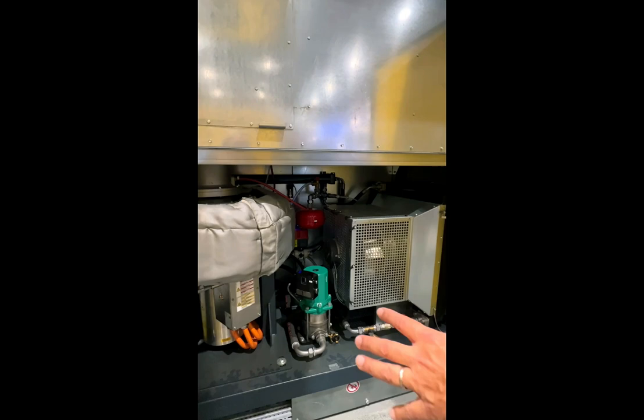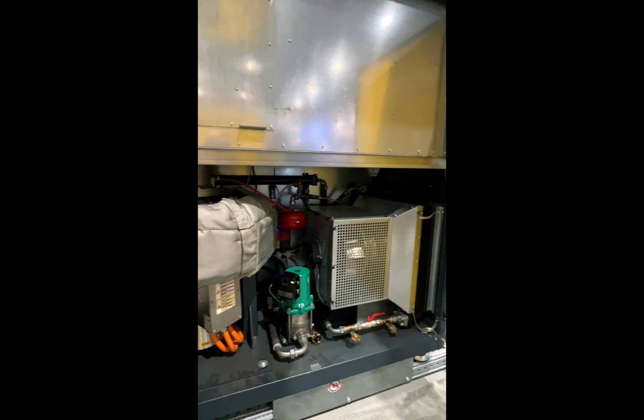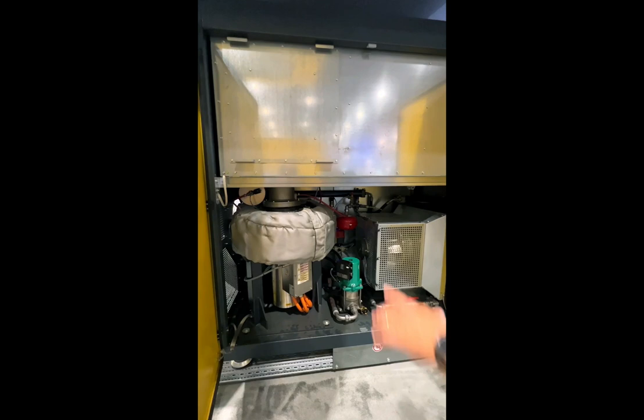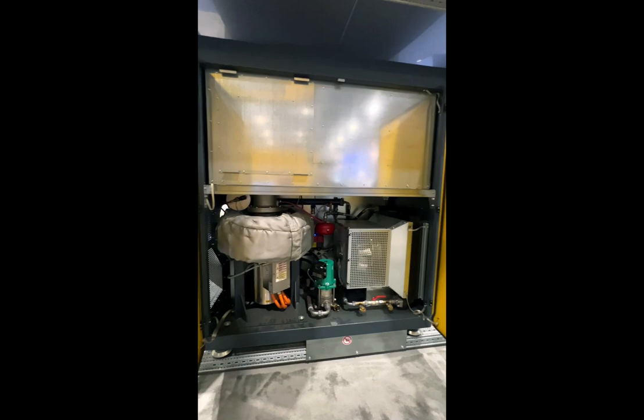Here is your motor and impeller combination. This is a magnetic-style bearing, so you have a shaft inside that motor levitating on a combination of permanent magnets and electromagnets. The electromagnets are controlled by the bearing controller on the opposite side. You're taking flow and temperature measurements here with transducers wired through the panel and back to the PLC. We have an inlet filter up here — this is the panel you'd remove to clean or replace the air filter, which has to be done on a regular basis. Those would be the primary components.